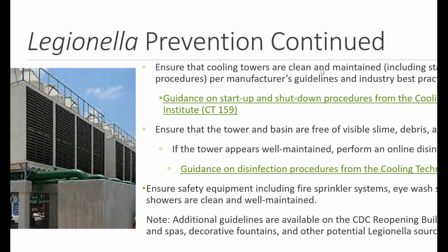Ensure the cooling towers are cleaned and maintained, including startup and shutdown procedures, per the manufacturer's guidelines and industry best practices. I have a link to the guidance for startup and shutdown. You want to make sure they're clean, no visible slime, no debris, no biofilms, very clean and well maintained. If it already looks that way, you would do a disinfection procedure, and again a link for the disinfection procedure that is the industry best practice.